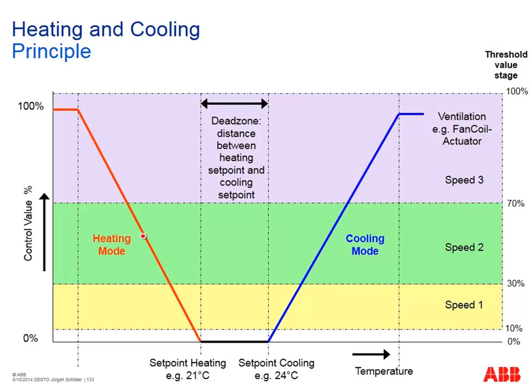So the first device I'd like to introduce you is a new device, a so-called blower actuator FCLS X611. X means it can be a 1 or 2, so with the device FCLS 1611 we can control a single phase fan, with up to 3 speeds. Here we have the connection to our fan up to 3 speeds, the incoming phase, and additionally a switch output. This switch output can be used independently of our fan, for example to switch on the light in a room, or maybe some of the fans need a kind of central command to switch on. So we can also control a central command to the fan input.